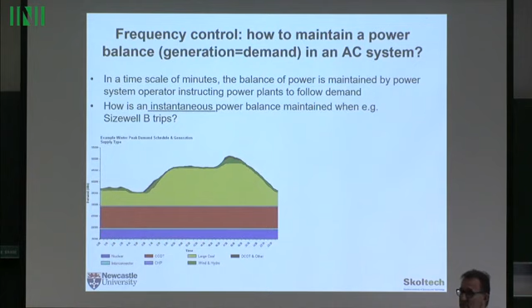Generation must equal demand at any instant of time. The power system operator doesn't know that something like that happened, and even if he did know, he couldn't have scheduled another generation to replace it immediately, because nothing works that quickly. So in the first instant, when you lose a large power station and there's a 1 gigawatt deficit, generation is less than demand by 1 gigawatt. What happens? How is this energy replaced, and by what?